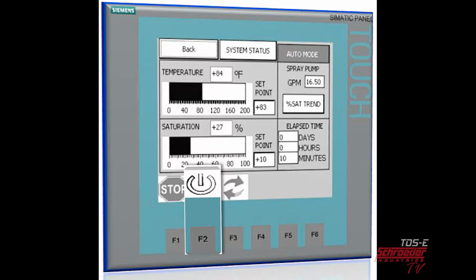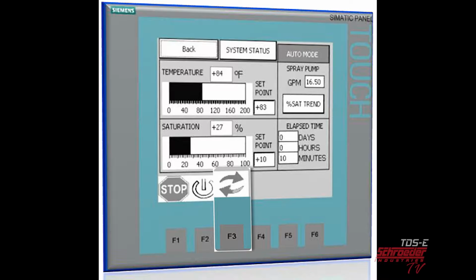It's only available on select screens. The F3 button is used to reset any system faults. We will review system faults later on in this video. Now that you know some of the basic support functions of the HMI, we'll go further in depth into the operation process. The default temperature and saturation set points need to be entered to run in automatic mode. Select set point under saturation and enter the value.